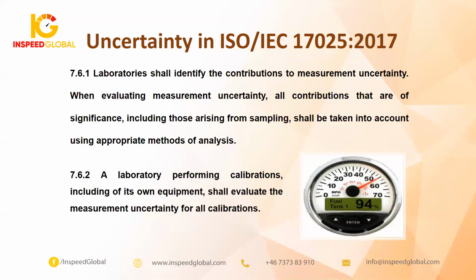7.6 is related to both laboratories, the testing lab and the calibration lab. Both calibration laboratories and testing laboratories are requested to estimate the uncertainty of their values, but for the calibration certificate it is also mandatory to mention the estimation of uncertainty in the final certificate. Okay.